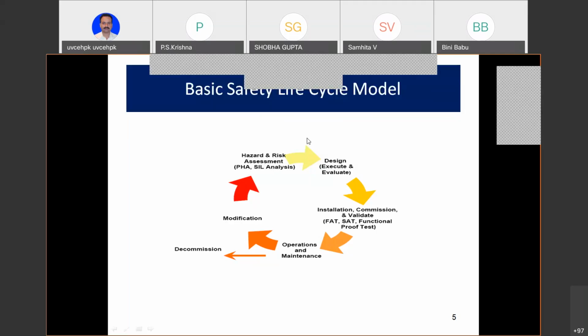We will not talk about it. Then we are going to the design, execute, and did we design? Yes. We put pressure switches, we put temperature switches, we put valves, we got that redundant programmable logic controller, and we got the trip logic, cause and effect diagram, all that. Then let us go and install it. We install it? Yeah, tomorrow we install it. We'll commission it? Yes. Now, let me talk about this commissioning.